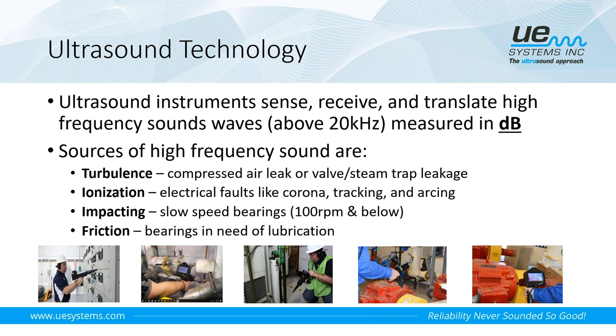And then there are different sources of high frequency sound. So we have turbulence. That turbulence can be either a pressure leak to atmosphere or air in-leakage, like a vacuum leak. You can also have internal turbulence across a valve or a steam trap. So if you have a valve that's leaking by, there's going to be flow that's restricted across that seat or orifice, and that in turn creates the turbulence that we hear with an Ultraprobe on the outlet or the discharge side of the valve. Ionization, the faults that we mentioned earlier with corona, tracking, and arcing, those are ionization-based faults that will produce sound that we're able to hear with an Ultraprobe.